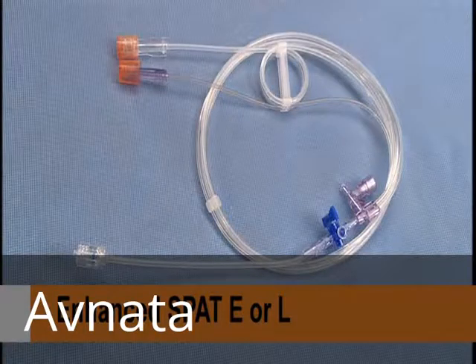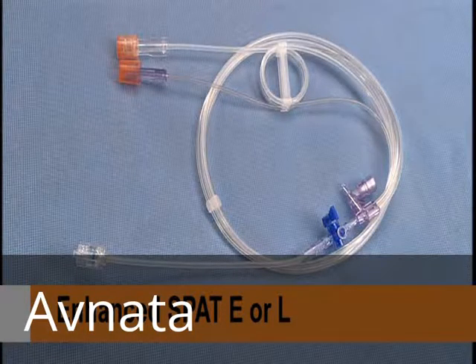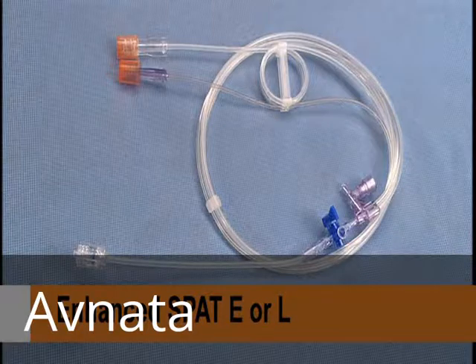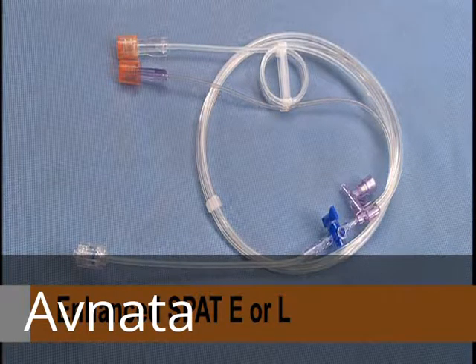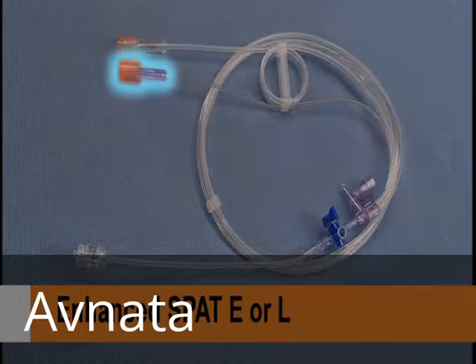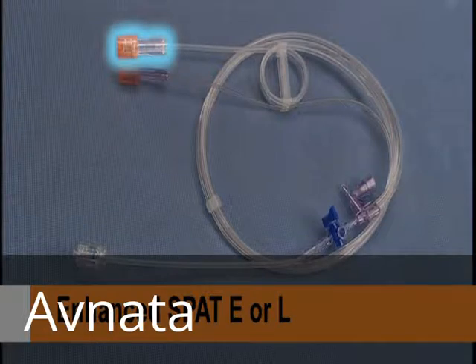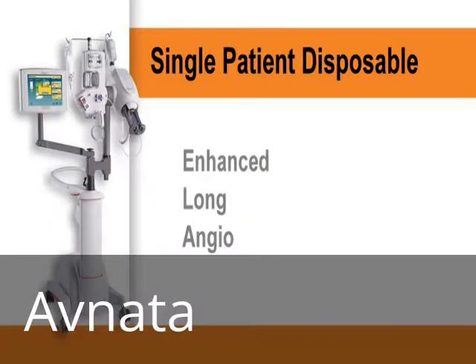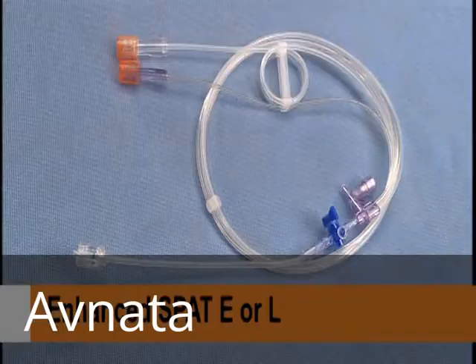The single-patient disposable, referred to as SPAT, consists of a dual line and is attached to the patient as one element. The SPAT dual line includes a high-pressure saline tube with male luer connector, and a high-pressure contrast tube with a female luer connector for easier connection to the MPAT disposable. The SPAT is available in 3 configurations: Enhanced, Long, and Angio.